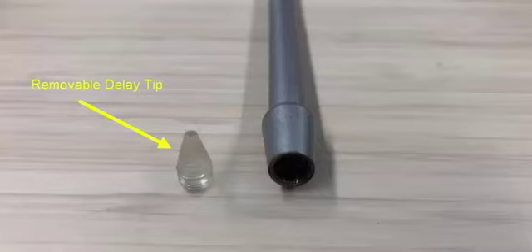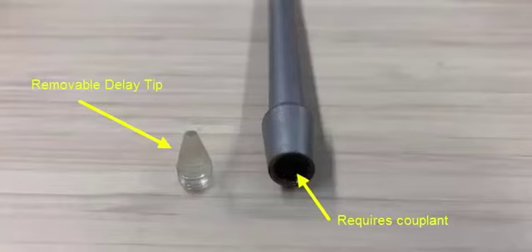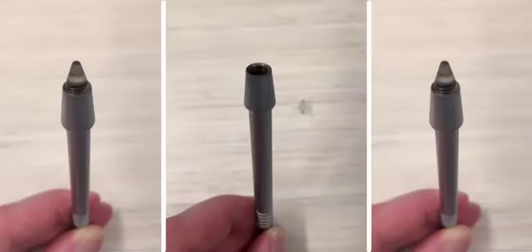Sonopens do not have permanent delay lines. The Sonopens require couplant under the removable delay line, since without it the sound will not be transmitted. Therefore, we recommend checking under the delay line tip to make sure there is couplant. To do this, the user would unscrew the delay tip. If it is dry under the delay line, the user should add a few drops of glycerin and then screw the delay tip back on.